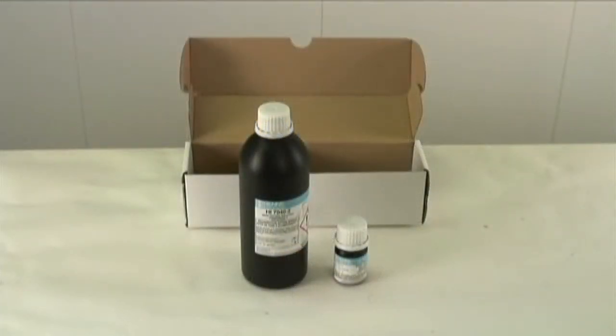The HI9142 only requires a 1-point calibration. These first 2 steps are optional, but will be useful if you plan on measuring in a low DO range. To perform a 0% calibration, you'll need to have handy the HI7040 Hanna Instruments Zero Oxygen Solution Kit. This won't be in your meter kit, so you'll want to purchase some along with the meter. The kit contains 2 components, HI7040-1 and HI7040-2.